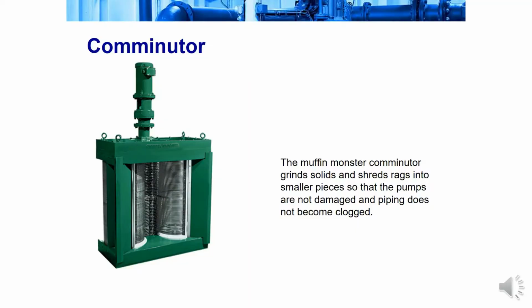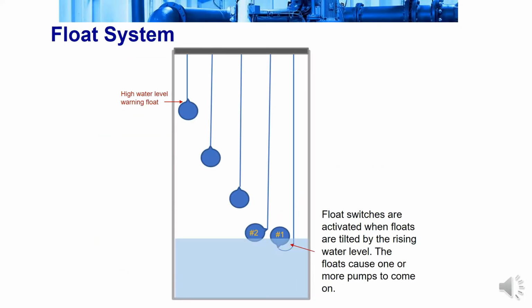The muffin monster comminutor grinds solids and shreds rags into smaller pieces so that the pumps are not damaged and piping does not become clogged through the course of wastewater treatment. Also within this intake area is a series of float switches. These float switches help command when the pumps turn on and when the pumps turn off. So as the water level increases, the pump switches are increased sequentially, allowing more and more pumps to be turned on. When the water level lowers, the pump switches disengage, allowing pumps to turn off and only be operated when commanded.